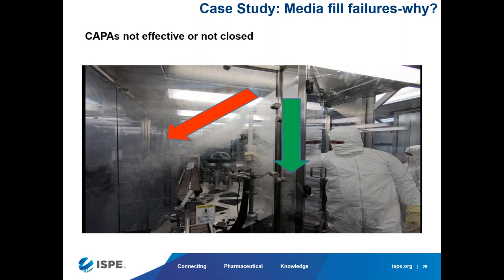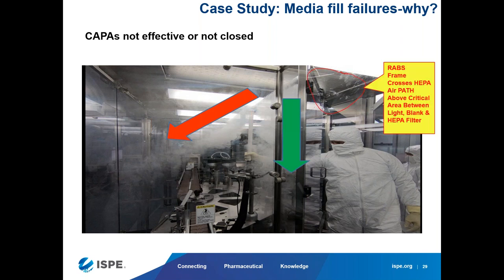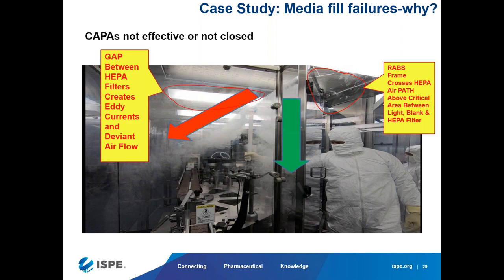This is a very good example. There were gaps, and you see the smoke going that way. The RABS frame crosses the HEPA air path above the critical area, between the light, the blank, and the HEPA filter. These are things that lead to a lot of 483s.